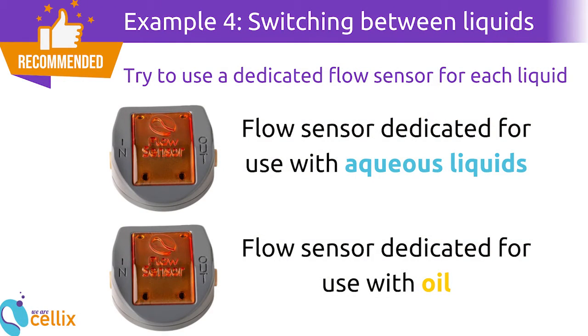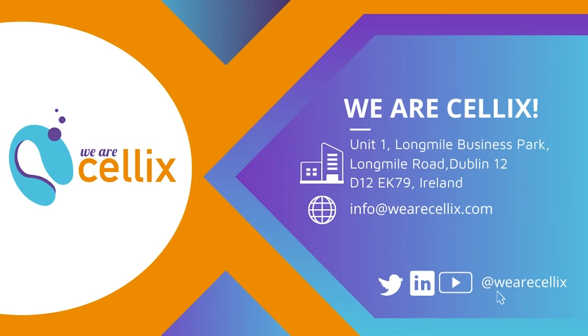Example 4. Working with multiple liquids. Switching between multiple liquids can leave transient deposits in the form of separated liquid layers inside the flow channel. We recommend a dedicated flow sensor for each different liquid. And that's it, you've just cleaned your microfluidic flow sensor.